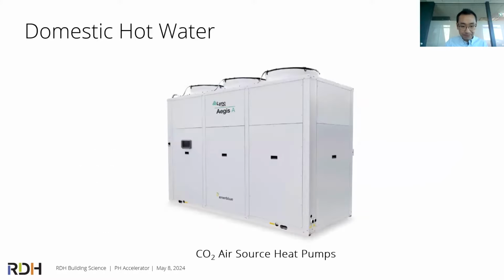For domestic hot water, we have CO2-based air source heat pumps. They offer high COPs with high lift capabilities, and CO2 is a natural refrigerant, so it's more attractive compared to traditional refrigerant systems like R134A and R410.